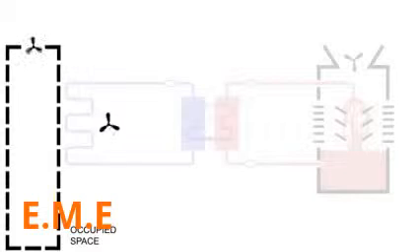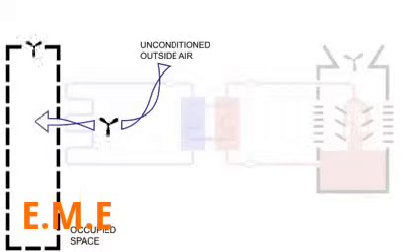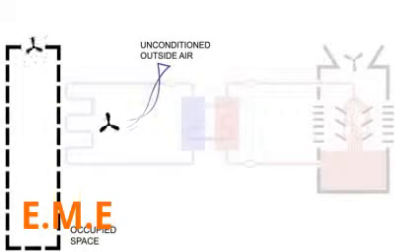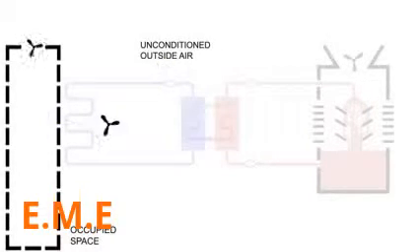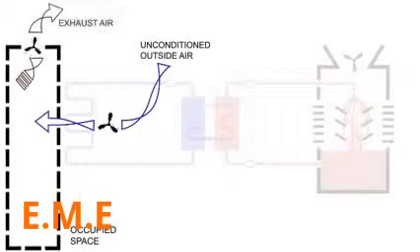In this case, in the air-side economizer, it may be more energy efficient to directly introduce cold outdoor air to the inside so your equipment doesn't have to mechanically cool the warmer recirculated air. As a side benefit, this offers superior indoor air quality. All that fresh air replaces what would otherwise be mostly recirculated air.